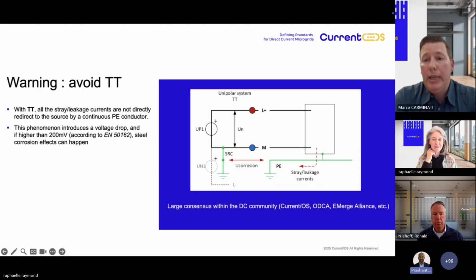Let's talk in particular about systems with an isolated interlink converter. You know, in DC, corrosion could occur because of stray currents. I remind you that stray currents are unwanted currents through an unintended path, like for example the reinforced concrete in buildings and through the ground, in particular where they go through the metallic pipes. Corrosion could occur when this stray current leaves the metallic part.